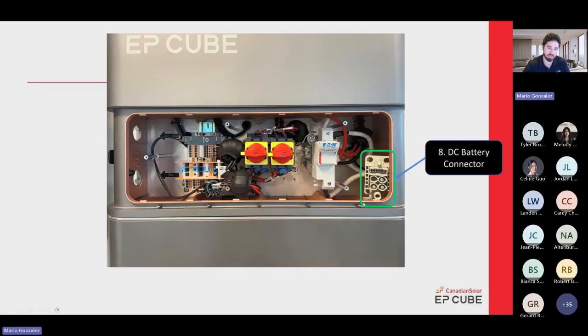Also very important, if you're not able to finish installation or commissioning, but you put the stack of the batteries, you install them, make sure this guy is disconnected or you remove the battery fuse. That way the batteries won't drain. Because I know things happen and you might not show up the next day to the job install, but maybe a couple of weeks later. Again, if you don't remove this connector or remove the fuse, the batteries are going to drain.